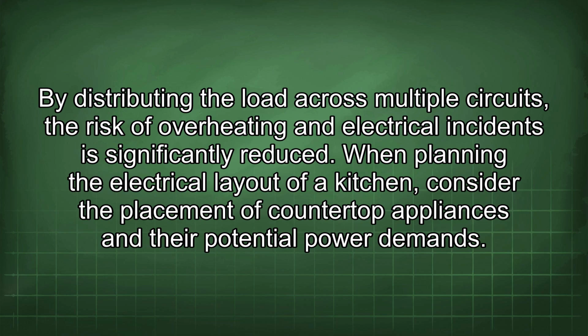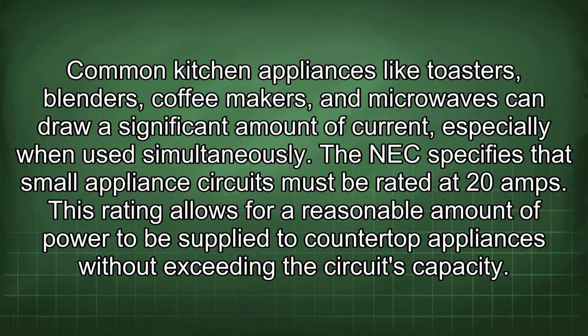When planning the electrical layout of a kitchen, consider the placement of countertop appliances and their potential power demands. Common kitchen appliances like toasters, blenders, coffee makers, and microwaves can draw a significant amount of current, especially when used simultaneously. The NEC specifies that small appliance circuits must be rated at 20 amps. This rating allows for a reasonable amount of power to be supplied to countertop appliances without exceeding the circuit's capacity.